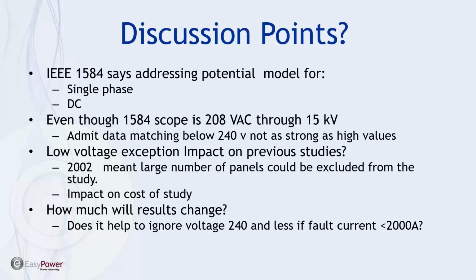For instance, there has been a history in arc flash compliance, if you will, in the direction of NFPA 70E and even in this standard 1584, that there's a migration path that has caused a lot of consternation with the changes from one revision to the next. And that requires a fair amount of investment trying to keep up with it. And what the IEEE 1584 committee says that they're gearing up for or expecting for the next revision is the potential for a single phase model and a DC model, neither one of which are included currently in the standard.